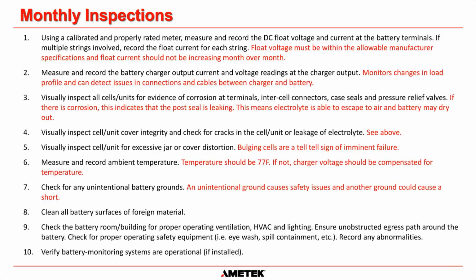Also, during a monthly inspection, you should visually inspect all the cells or units for evidence of corrosion at the terminals and on the intercell connectors, and look at the case seals and pressure relief valves and make sure they're clear of debris, there's nothing covering them, and that the relief valves have the ability to allow gas to expel if necessary. Okay, if there is corrosion, that indicates that there is a post seal leaking. And in a valve regulated lead acid battery, if there's a post leaking, that means pretty much the battery is going to die eventually, because the water inside the electrolyte is escaping from the cell through that post seal leak, because it's not going through the recombination process.